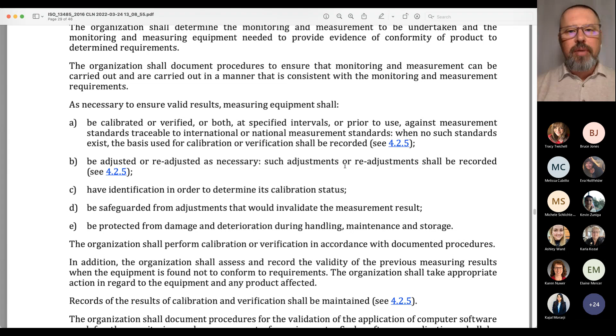This paragraph here talks about if you find out that a piece of equipment was not performing as expected. So you perform a calibration and the as received or the as found calibration fails, then this says that you're going to perform what we usually refer to as an out of tolerance investigation. And part of that out of tolerance investigation has to be an impact assessment for the product that you were monitoring and measuring with this device that was not functioning the way you thought it was.